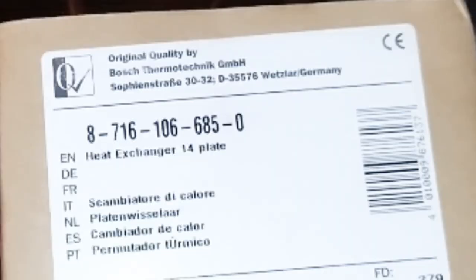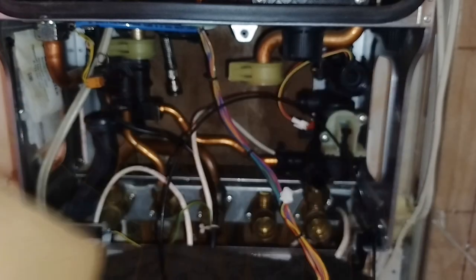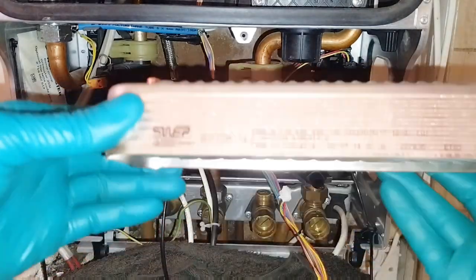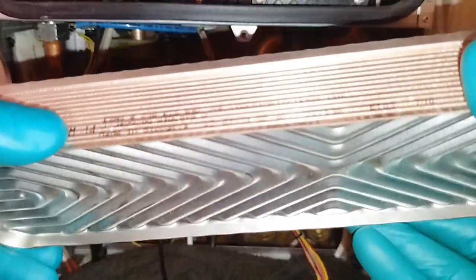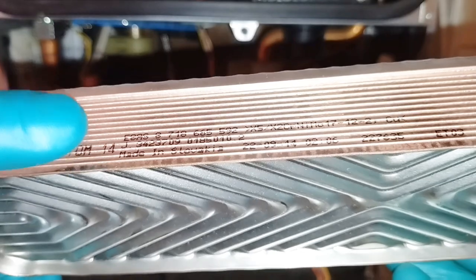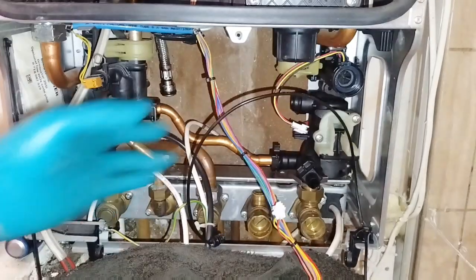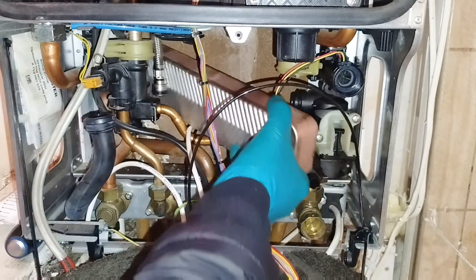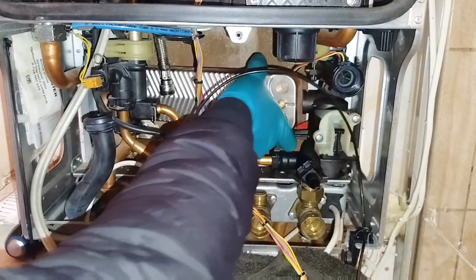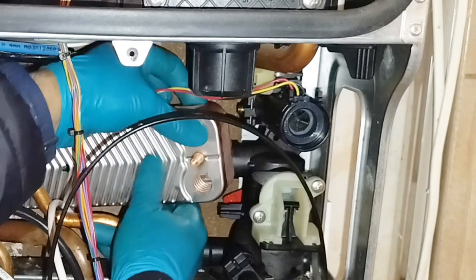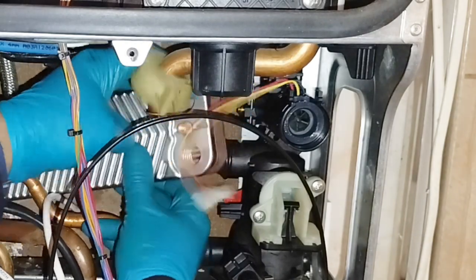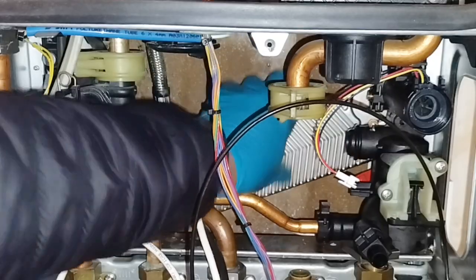So this is the new plate heat exchanger, and this one, different from the other one, is a 14 plate heat exchanger, so it's slightly bigger. It allows more rust to accommodate in the plate heat exchanger, so even if the system's a bit dirty, not being cleaned, it's got a bit more space. Obviously if you've got space behind the boiler to put a thicker plate heat exchanger, then why not put a bigger one which will have less trouble.